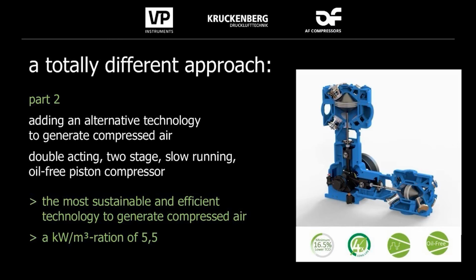And the biggest advantage of this technology is that it is much more energy efficient, much more sustainable, because compared to oil-free two-stage screw compressors, it's lasting 4 times longer. You can regulate these pistons in the same way as a VSD-driven screw compressor. They're 100% oil-free, and they provide a solution which is reliable for decades. And they have much lower repair or maintenance costs, because the maintenance intervals are every 8,000 to 10,000 running hours, depending on the conditions at the client.